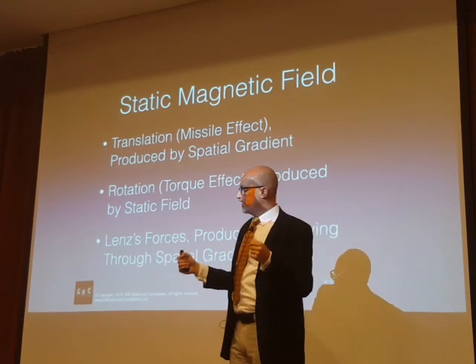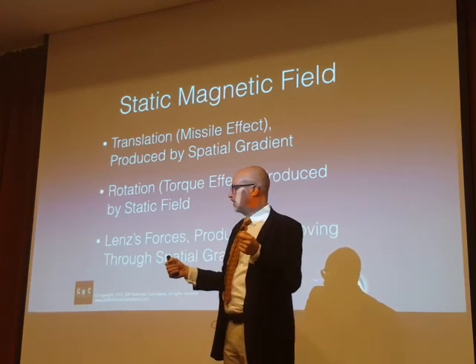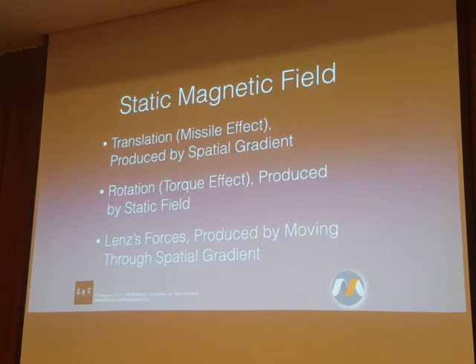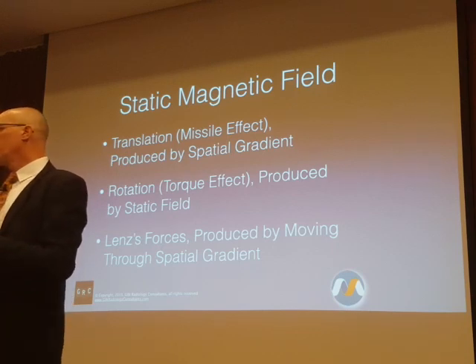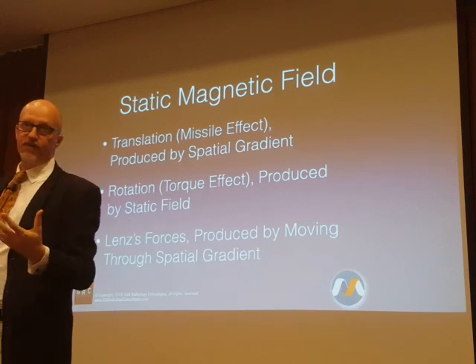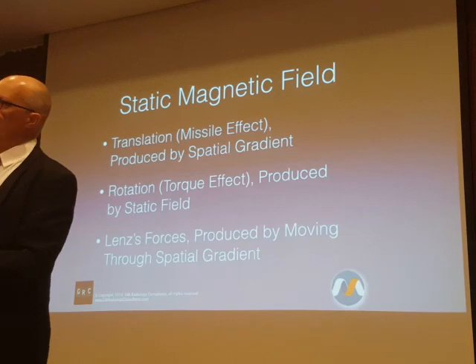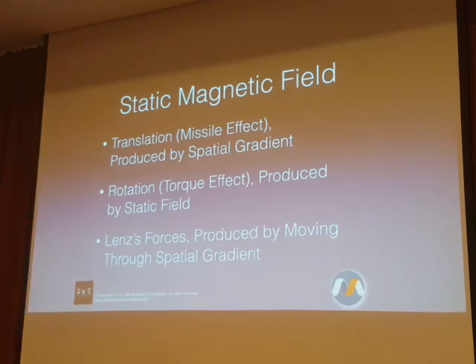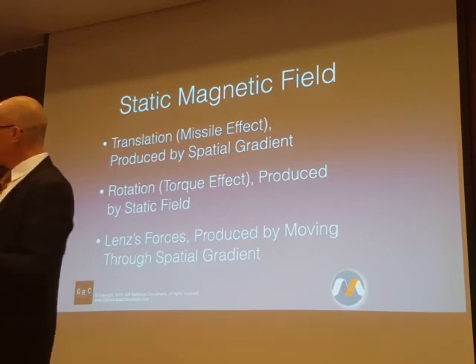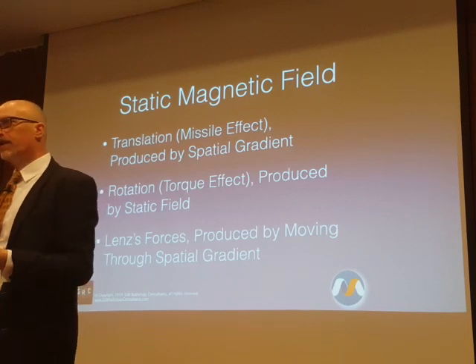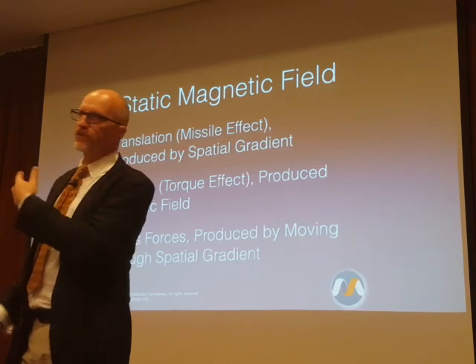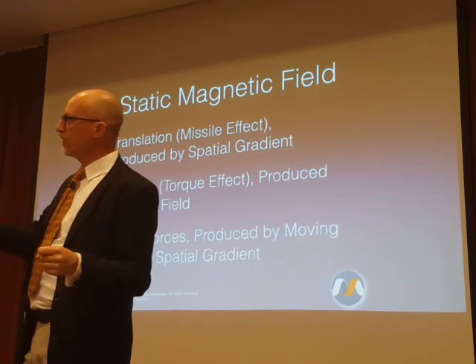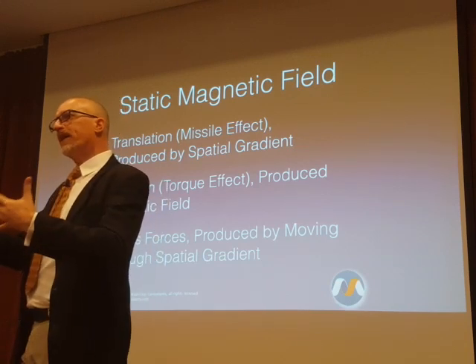I come with a large electrically conductive material, an aluminum pie pan, and I start moving towards the opening of the MRI, where the spatial gradient is the greatest at the mouth, the front end and the back end. As I am moving towards this, I'm moving an electrically conductive material through a magnetic field. Faraday's law of induction: when you move an electrical conductor, a material with low resistance to the flow of electrons, through a magnetic field, that action induces a voltage in that material. Like what we talked about, the large caliber body loop and the radio frequency inducing a voltage, the bigger the circuit, the bigger the pathway, the greater the induced voltage.